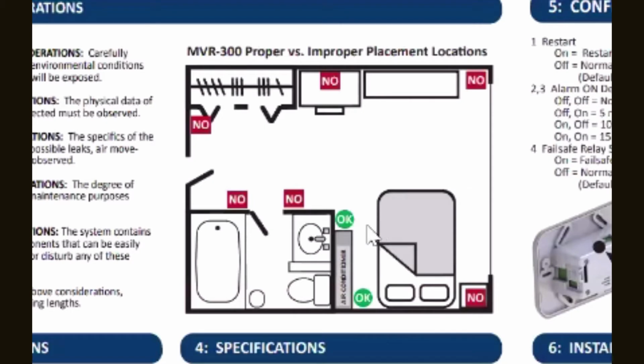Typically, our range is somewhere from 6 to 18 inches off the floor. 12 inches is a real good spot. You could even go a little bit lower with that, but 12 inches is probably going to work. Now, you want to put the gas detector near the source and preferably in the ambient airflow. And if you're seeing my screen, the air conditioner ambient airflow is going to be across the bed and out the door, or there's going to be some sort of cold air return near the door. So this ambient air is typically going to flow towards the door. So good place for the gas detectors are right near the VRF systems.